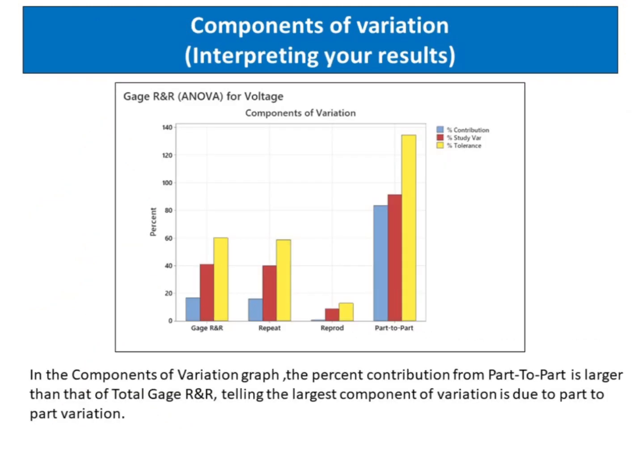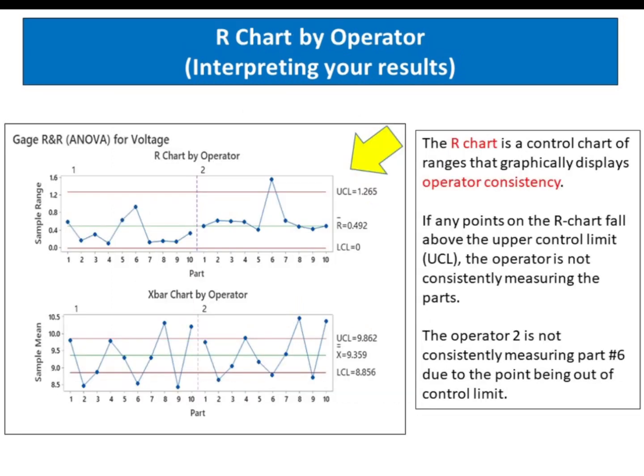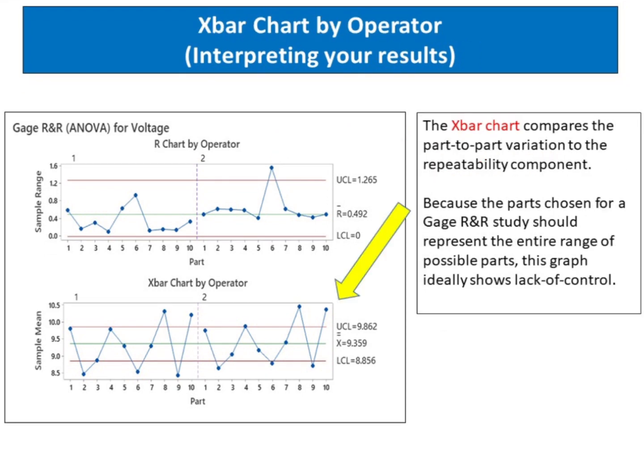In the components of variation graph, the percent contribution from part-to-part is larger than that of total gauge R and R, telling us the largest component of variation is due to part-to-part variation. The R chart is a control chart of ranges that graphically displays operator consistency. If any points on the R chart fall above the upper control limit (UCL), the operator is not consistently measuring the parts. Operator 2 is not consistently measuring part number 6 due to the point being out of the control limit. The X-bar chart compares part-to-part variation to the repeatability component. Ideally, the graph has narrow control limits with many out-of-control points, indicating a measurement system with low variation.